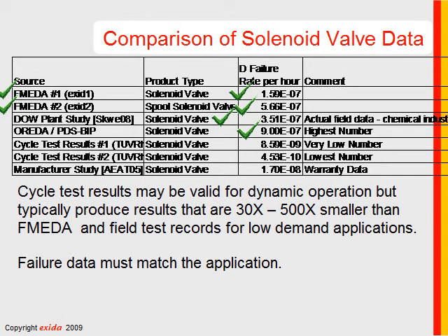And I have to admit I was very curious as to why that was. And I did travel up to Norway and have a meeting with the people who analyzed the OREDA data. And it became very clear that OREDA includes what I call site-specific data in their reports, whereas FMEDAs include only failures due to the product. Now, what does that mean?